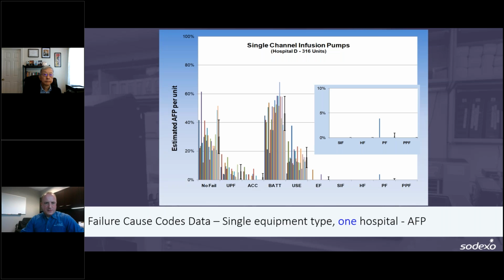So failure cause codes here, we have single channel infusion pumps. This is, again, at one hospital, and this is showing us 24 months. On the left-hand side, you can see that no problem found is about 30%, while battery use is 45 to 50% of the problems. This is a snapshot of your equipment for the current maintenance strategy. If you change maintenance strategies, this will become your baseline for determining the effectiveness.